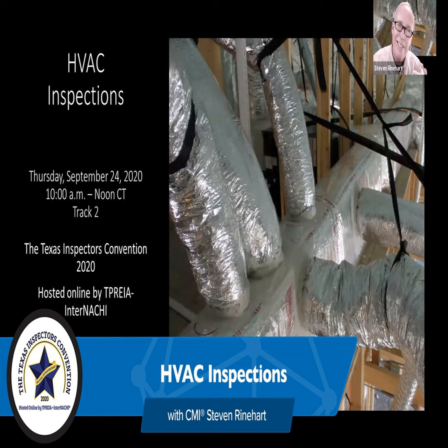There are some prohibited areas, obviously sleeping rooms and bathrooms, toilet rooms, storage closets. And we're talking those rooms plus rooms that communicate air, like a bedroom closet. You can't say the closet's not in the bedroom. It is. Same with bathrooms.